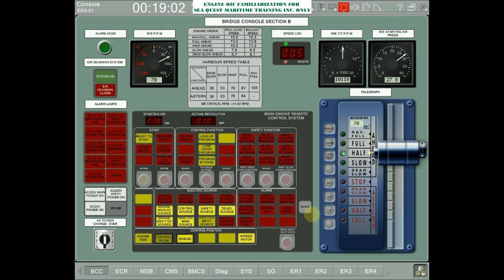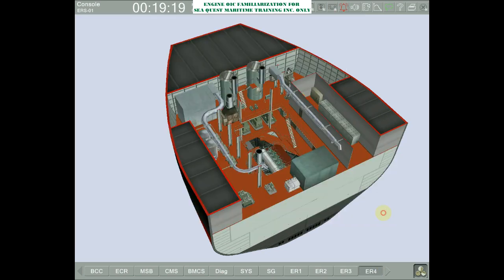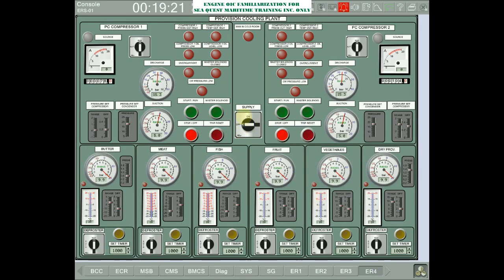Alright, then go to ER4, select, we start the required auxiliaries. So we will start with provision cooling plant, go to ER4, choose provision cooling plant LOP, switch on the power supply, and press master solenoid valve, number 1 and number 2 compressors, and press the start button.